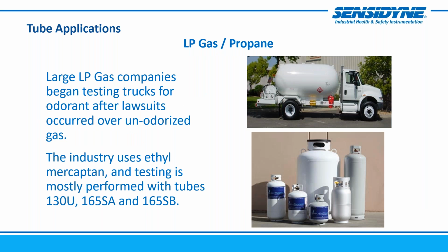In LP gas, as most of you know, if you've ever smelled LP gas, you're not actually smelling the liquid propane. What you're smelling is a mercaptan that is added to the propane, obviously as a safety precaution. So this is one of those instances where we have specific tubes that can measure mercaptan. I'm just using this as an example. Sometimes certain chemicals are added within a system, and you want to make sure that it's at the appropriate level and concentration within another gas stream. So the use of these gas detector tubes can help determine that concentration level.